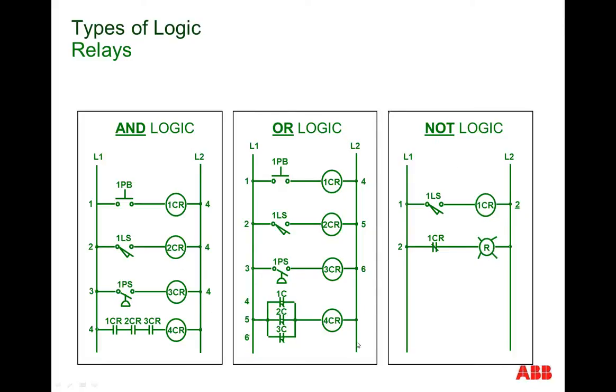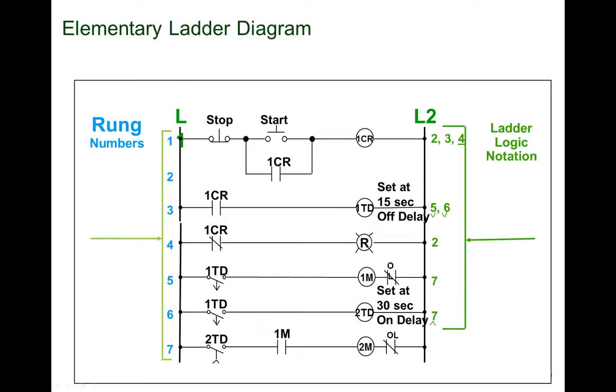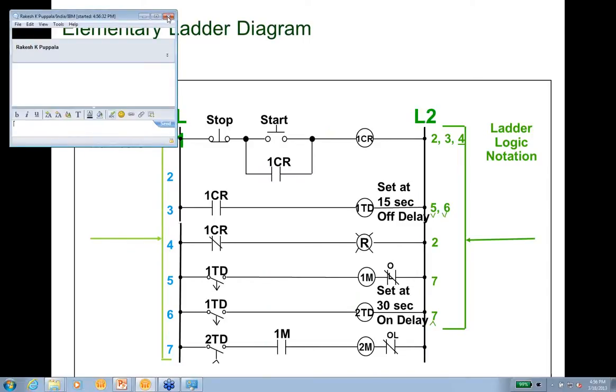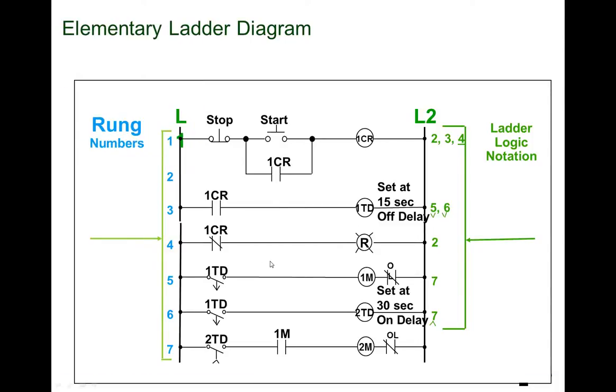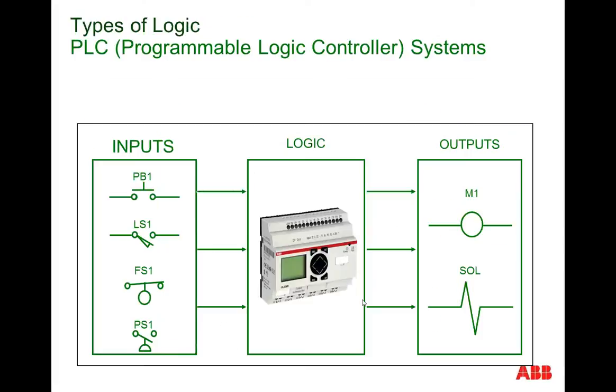Now what's interesting is that electricians will take hundreds of these devices and interwire them to form some fairly complex patterns of Boolean logic. And you can see here, here's a simple relay ladder diagram that can actually get quite complex should you have a large control system or a large machine that you're wishing to control. Now you'll see here also a nomenclature where we're numbering the rungs, and we're allowing an electrician to go and troubleshoot a system should there be a problem with one of these timers or one of these relays.